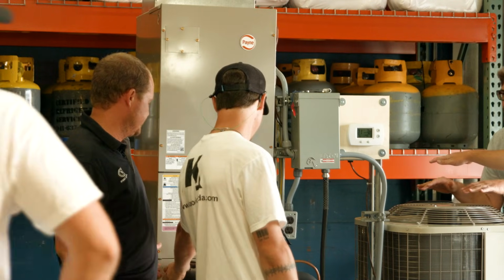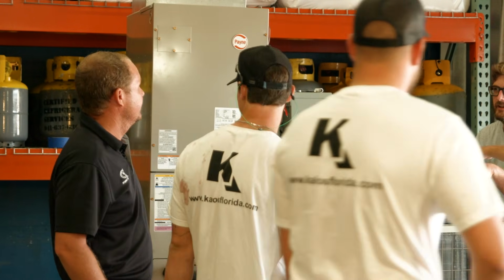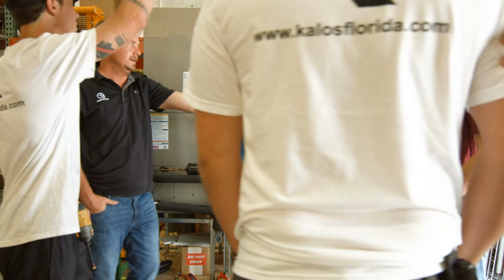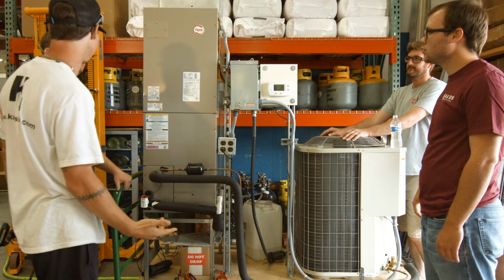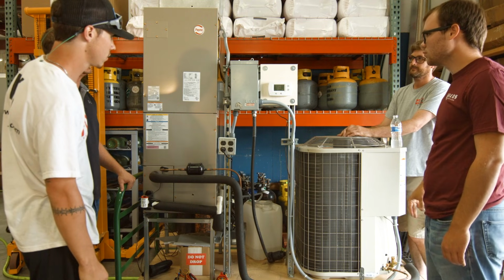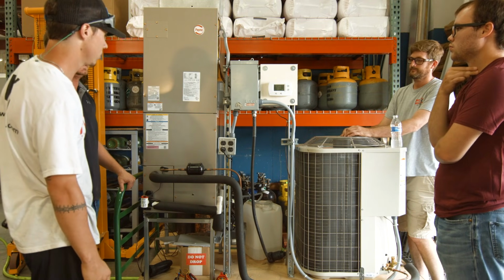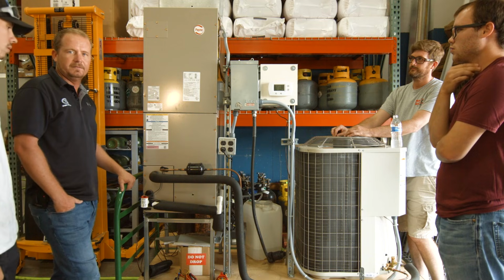So what are you doing? Just touching to see, just to make sure the reversing valve switched over correctly. So you're going to feel heat here, you're going to feel cold. So it is running in heat now too. So for some reason it was energizing the reversing valve even when we had it set up for a straight cool unit, which is kind of interesting.